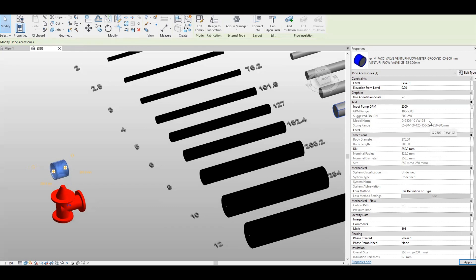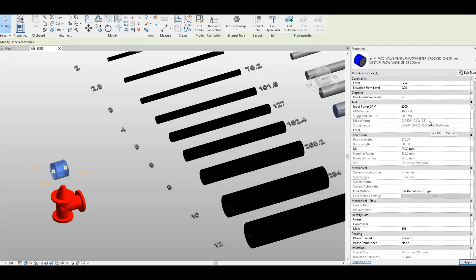This family has added value with metric and imperial system support, meaning it will read the discrepancy of decimal points between the imperial and metric systems — inches to millimeter. So if you convert the project from inches and change the unit to millimeter, some pipe sizing will have decimal points because there's no perfect conversion between imperial and metric. That's why this family is already set up to handle reading both the imperial and metric system.